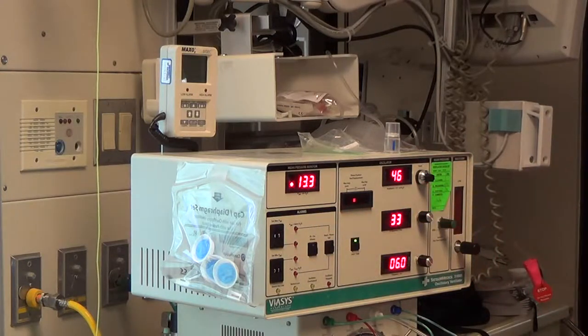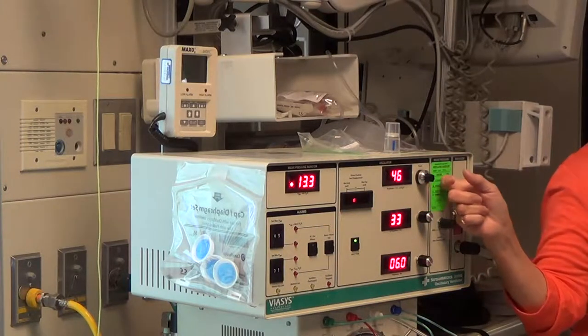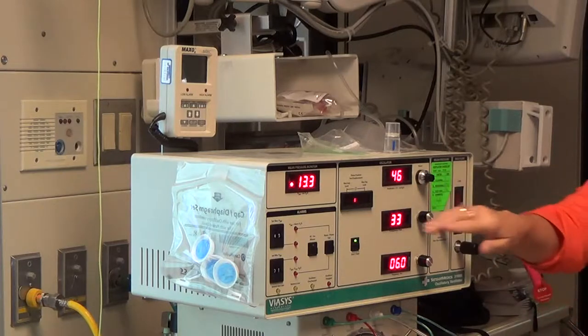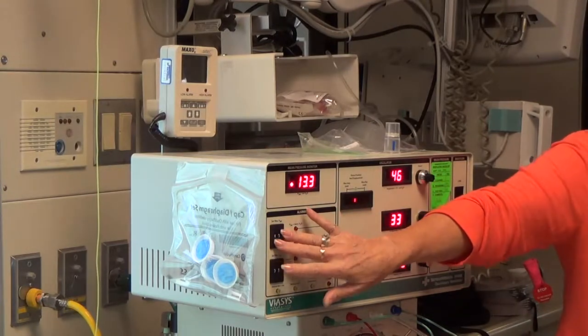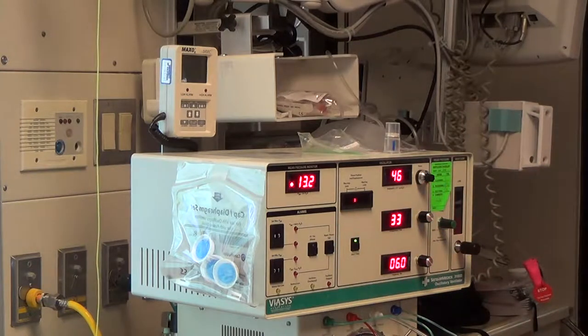You guys have all used the A? Your limit is here, that blue knob. In the B, your limit is here. It's very, very important that you set that, because remember, when we set this up, it's set at 59. If you don't fix that first breath on that patient, and he wakes up, I can give that patient 60 centimeters of water pressure. Very, very important concept. You guys all know that? Know that that's your limit. It's a big aha moment, okay?